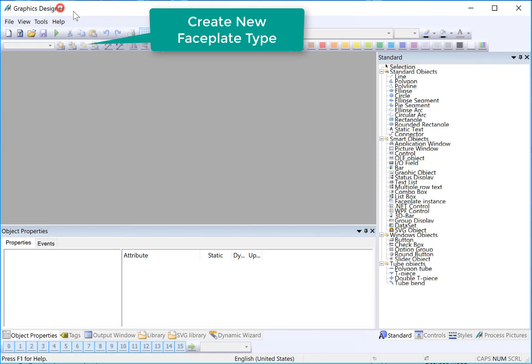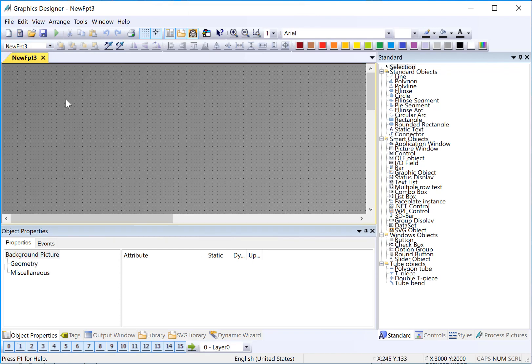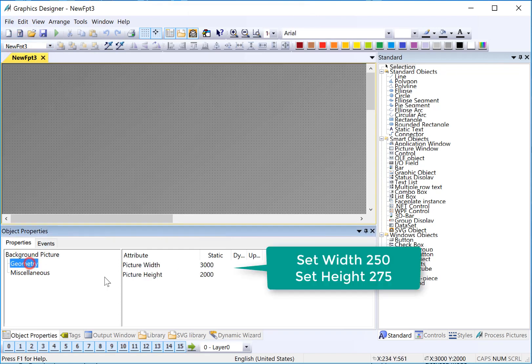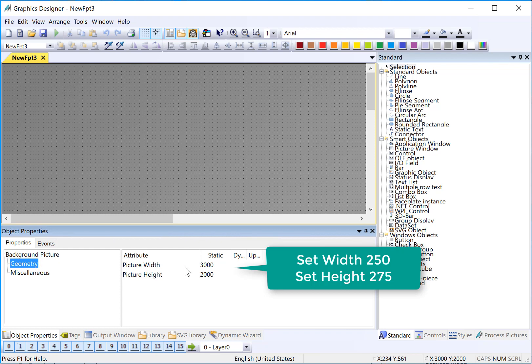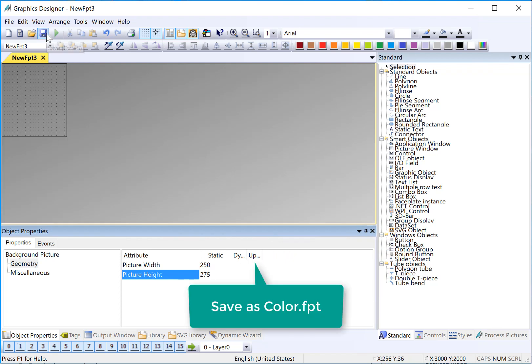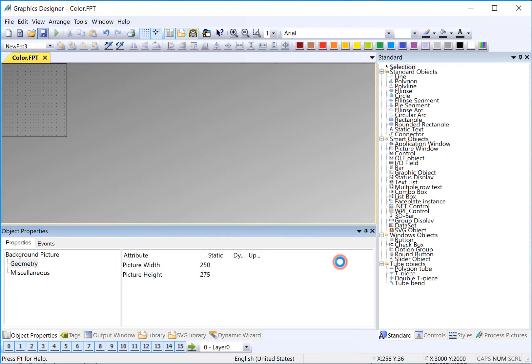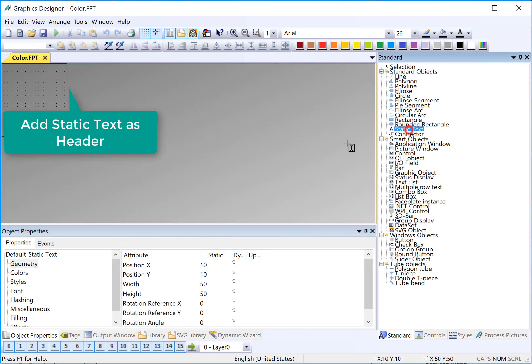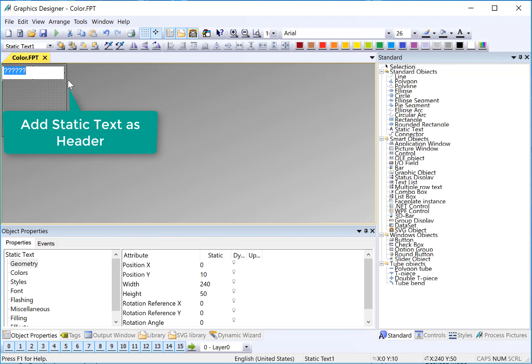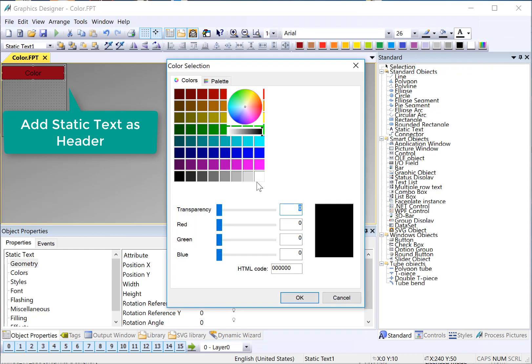We're going to start in Graphics Designer. I will choose File, New Type, and it will create a new faceplate instance. I'll go to Geometry. I'll set my width to 250 and my height to 275. Then I'm going to save. We'll save this as color faceplate. Next, I'll grab a static text object to make our header. And I'll just default the text to color and just give it a background color and set my font to white.